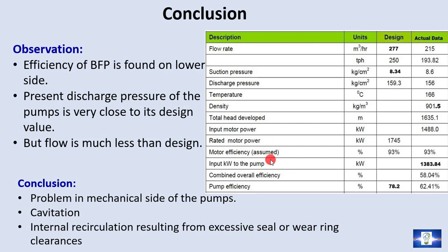As more water is recirculated, it heats up due to friction and eventually vaporizes and condenses repeatedly. Pump capacity and efficiency are severely reduced during cavitation, and permanent damage from cavitation results in permanent capacity, efficiency and head losses. So friends, in this case a pump overhaul or pump maintenance is required to enhance the efficiency of the boiler feed pump.